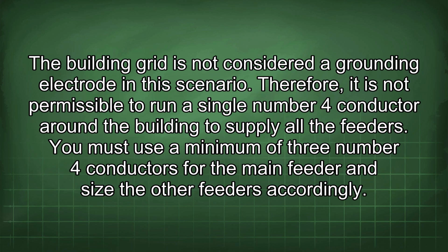The building grid is not considered a grounding electrode in this scenario. Therefore, it is not permissible to run a single number 4 conductor around the building to supply all the feeders. You must use a minimum of 3 number 4 conductors for the main feeder and size the other feeders accordingly.